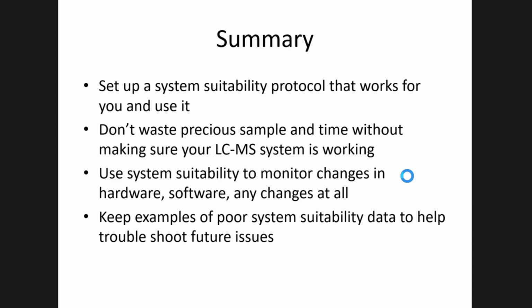You have to evaluate a good amount of data and then set up your confidence intervals. And that's why using software like SProCoP or AutoQC, I think, has it in there. If you're starting with nothing, make a bunch of measurements. Don't just rely on 10 injections one after the other. Do that, but then do it once a day for a number of days. And then once you get enough data to be able to confidently define your acceptance criteria, then you're good to go.